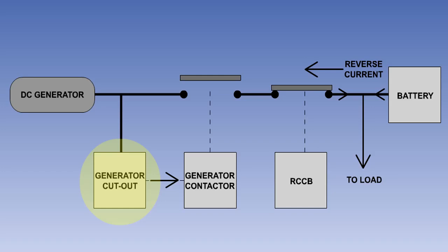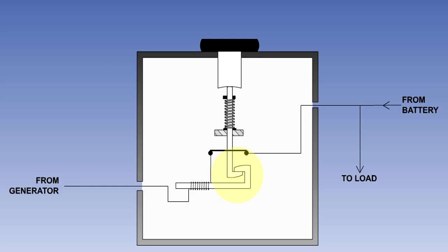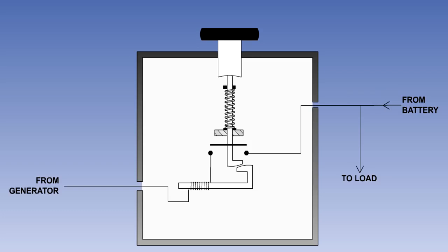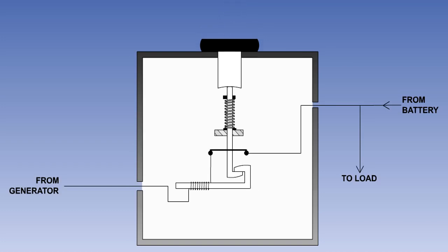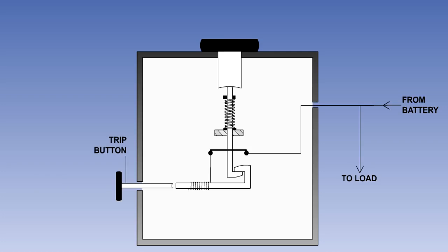In order not to interfere with this process, the reverse current required to operate a reverse current circuit breaker is high, usually more than 200 amperes. The reverse current circuit breaker contains a latch mechanism, which is holding a set of contacts closed. The latch mechanism is held closed magnetically. A coil wound around the latch mechanism produces a magnetic field, which helps to hold the mechanism latched when the current flow is in the normal direction. However, when the current flow through the coil is reversed, its magnetic field operates in the opposite direction. At a preset current level, this field will have sufficient force to break the latch and open the contacts. Once tripped, an RCCB can only be reset by pushing the manual reset button. There is usually also a manual trip button on the unit.